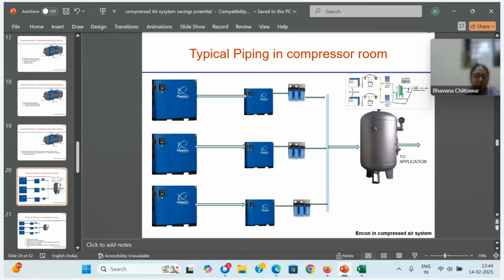Next, typical piping in the compressor room. Generally, the majority of the compressors' piping has been designed by the compressor suppliers. They are all idiots actually who recommended this. So they install compressor, dryer, dryer to oil filter, then it will go to receiver, then issue to application. This is how it is. And there are inbuilt dryers also. Here, if the dryer is faulty, you cannot run the compressor. If the compressor is faulty, you cannot run the dryer. If oil filters are faulty, you have to close the entire circuit. There will be huge pressure drop in this.